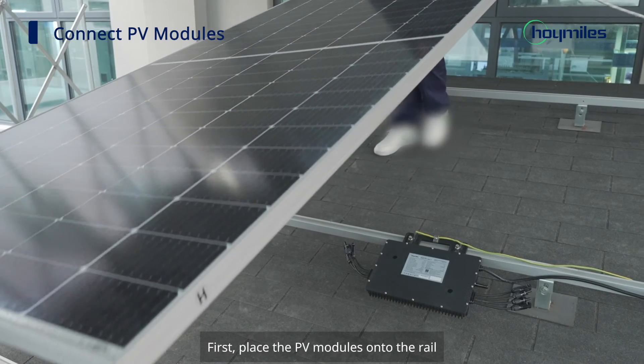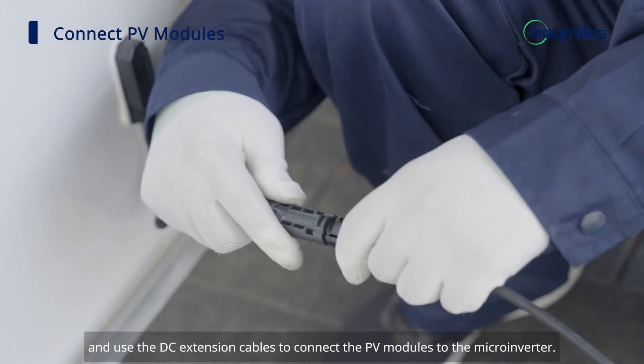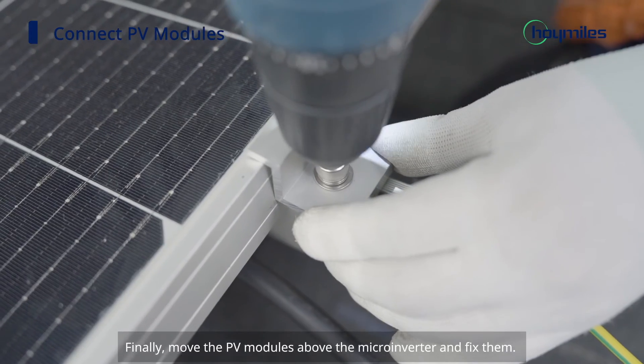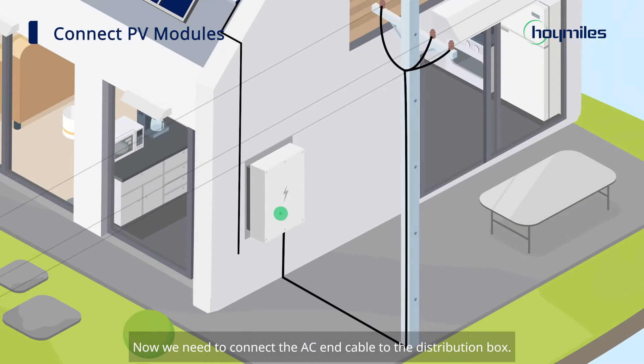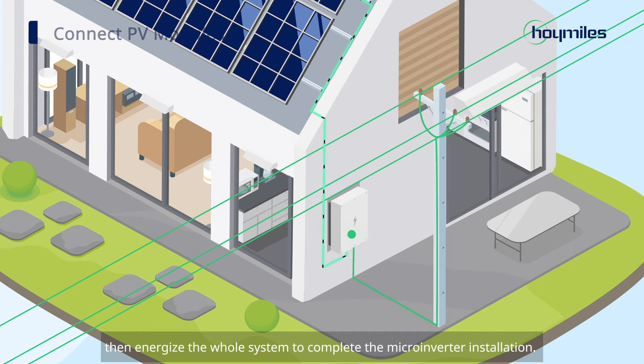First, place the PV modules onto the rail and use the DC extension cables to connect the PV modules to the microinverter. Finally, move the PV modules above the microinverter and fix them. Repeat the above steps to connect all PV modules. Then connect the AC end cable to the distribution box. After obtaining the permit from the grid operator, energize the whole system to complete the microinverter installation.